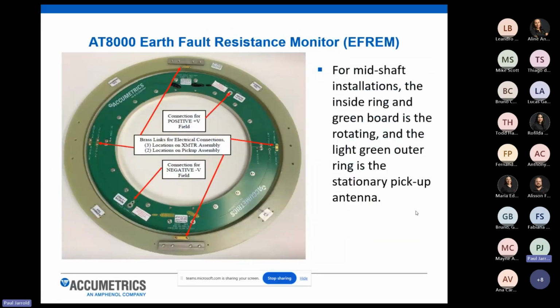So this is the EFREM mid-shaft telemetry system. The inner green ring is the rotating transmitter. That will be bolted directly to the brushless exciter and rotating with the machine. The outer ring is our stationary pickup antenna. So this is what's forming essentially those 2 hoops of wire, that rotary transformer connection between the rotor and stator.